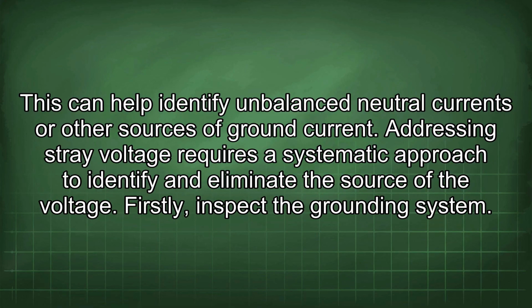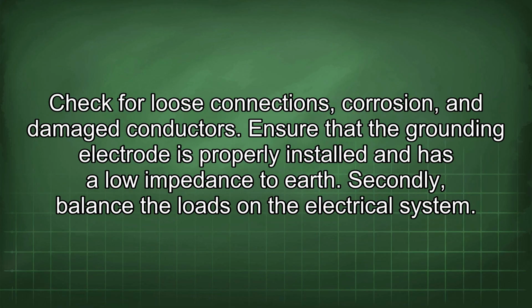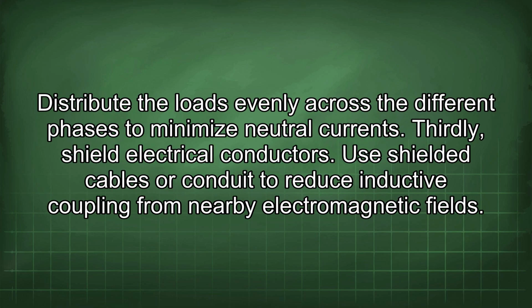Addressing stray voltage requires a systematic approach to identify and eliminate the source of the voltage. Firstly, inspect the grounding system. Check for loose connections, corrosion, and damaged conductors. Ensure that the grounding electrode is properly installed and has a low impedance to earth. Secondly, balance the loads on the electrical system. Distribute the loads evenly across the different phases to minimize neutral currents.